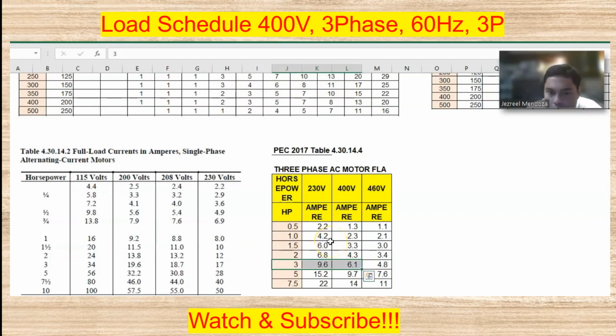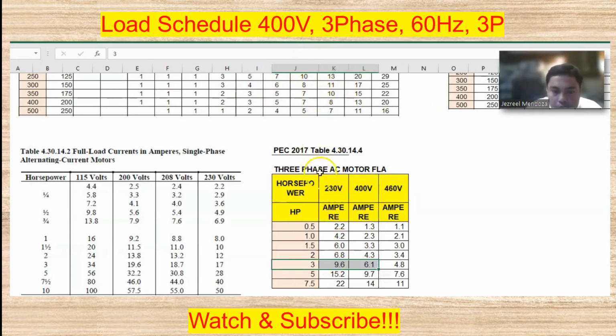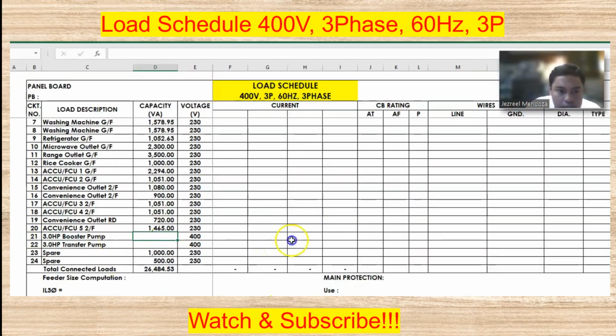And then yung 3 HP na motor, ang full load current niya sa 400 volts falls to 6.1 amperes. And then let's use that, this one, that is 3 phase, 6.1 amperes.